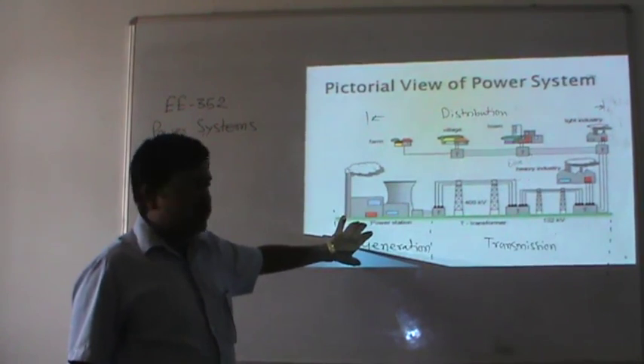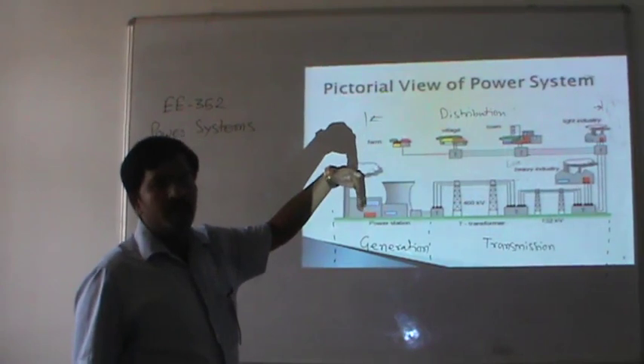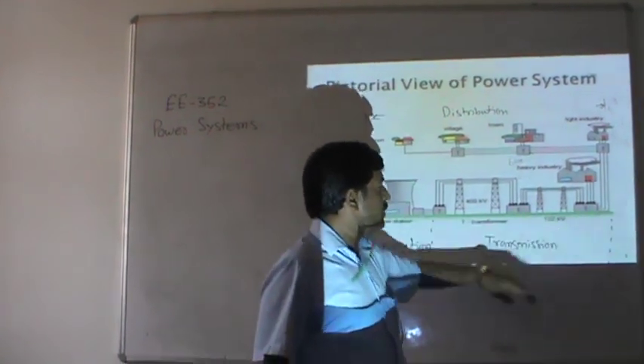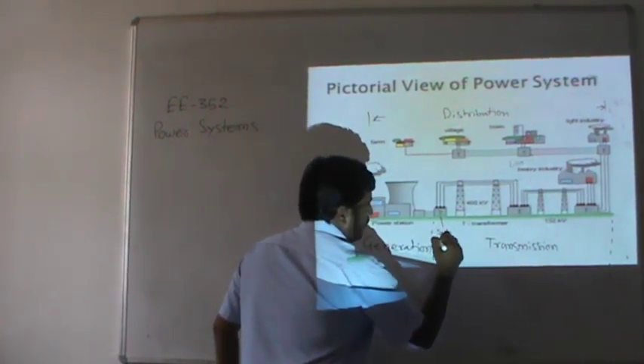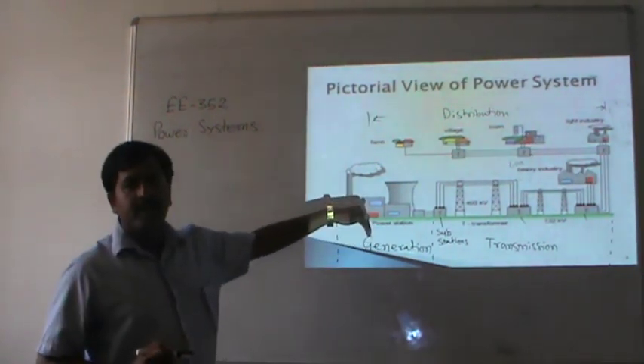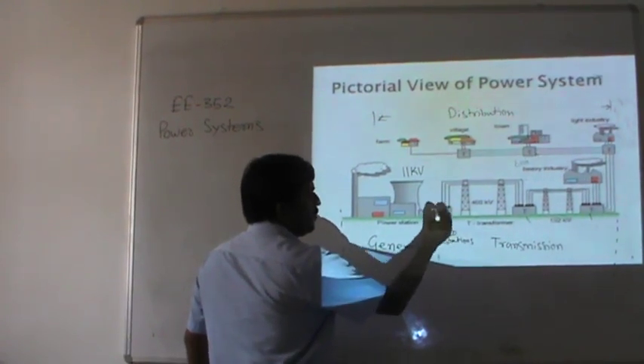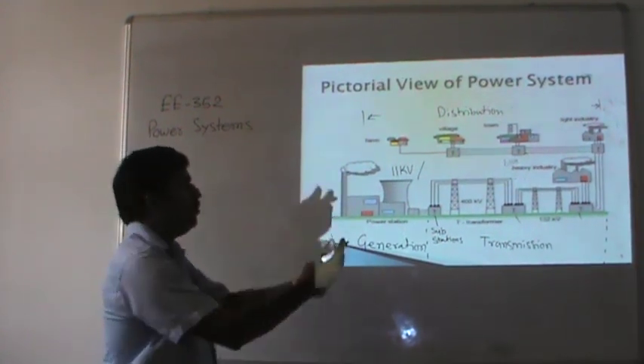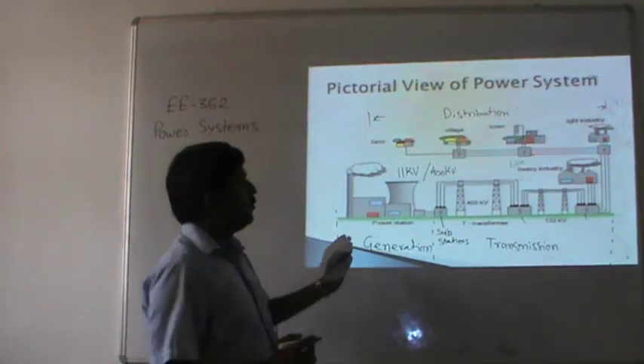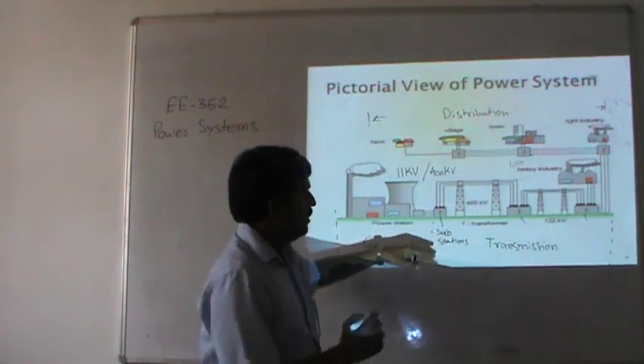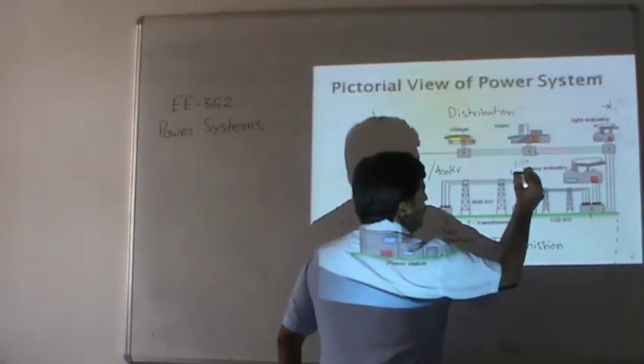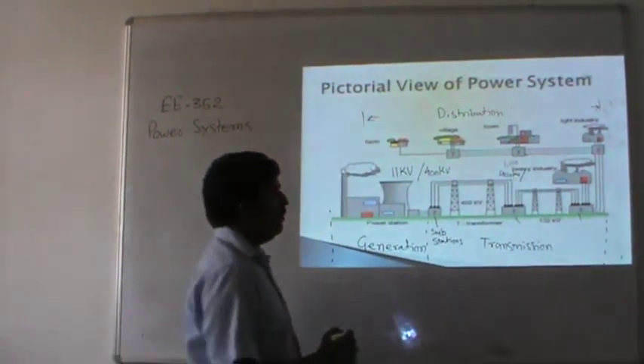Energy is generated at the power station and a high voltage is transmitted through the transmission line. Here you can see a 400 kV transmission line that is stepped down to 132 kV at substations. Electricity is generated at 11 kV, and with the help of a transformer it is stepped up from 11 kV to 400 kV for long-distance transmission. The substation nearer to the load center steps the voltage down from 400 kV to 132 kV.